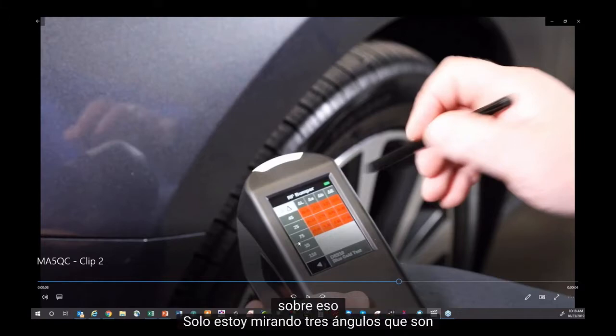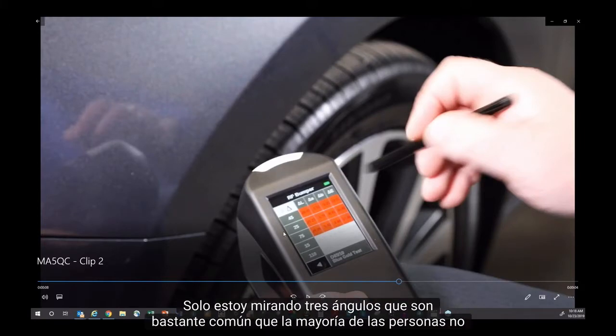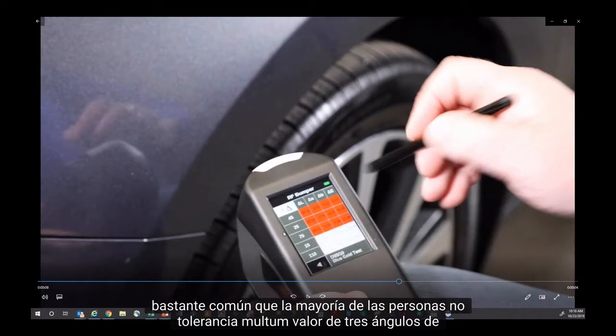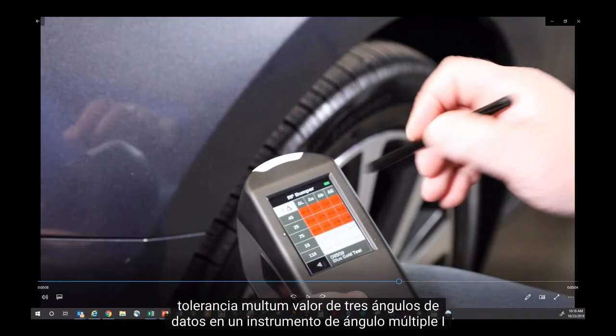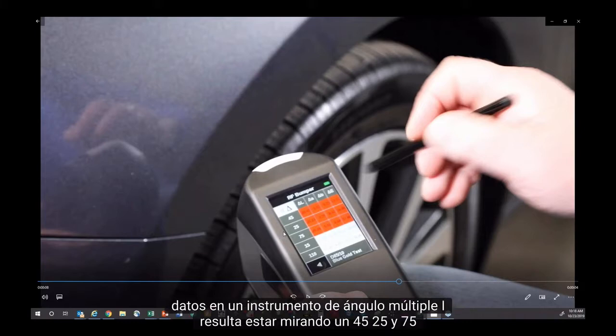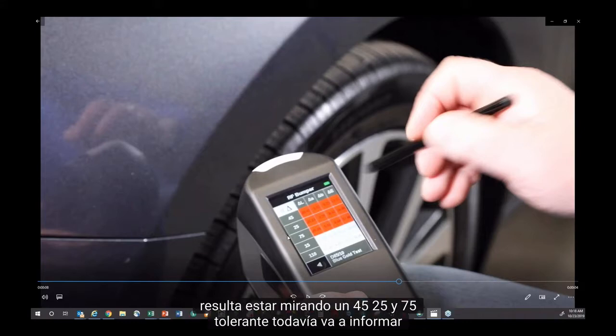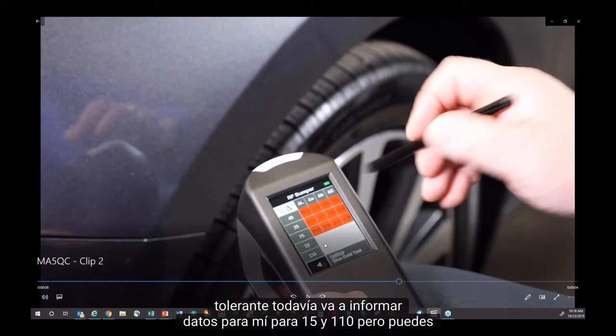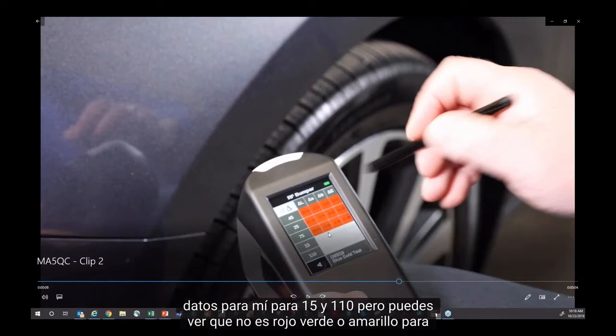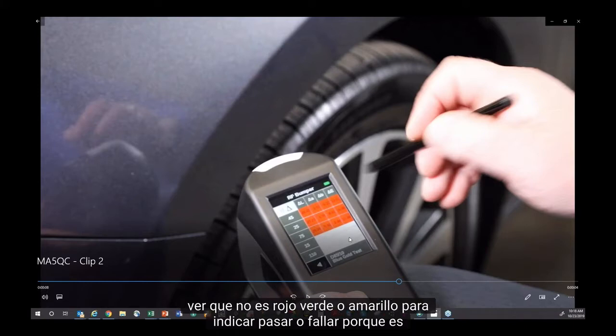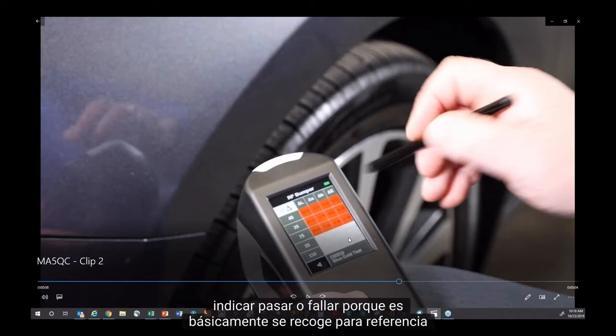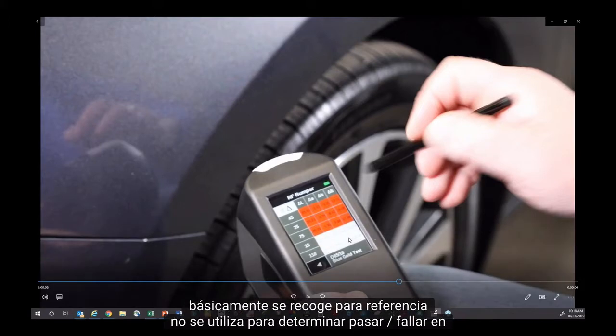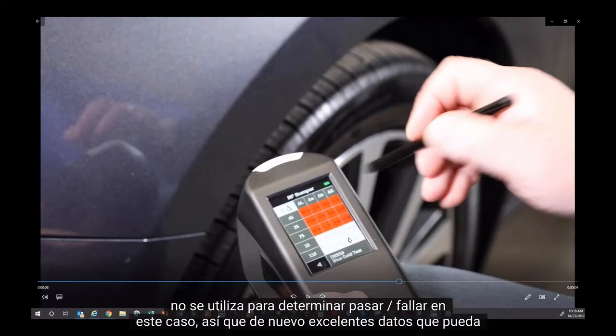I'm only looking at 3 angles. That's fairly common. Most people don't tolerance more than 3 angles' worth of data on a multi-angle instrument. I happen to be looking at a 45, 25, and 75 tolerancing. It's still going to report data for me for 15 and 110, but you can see it's not red, green, or yellow to indicate pass or fail, because it's basically being collected for reference, not being used to determine pass-fail in this case. So again, great data.